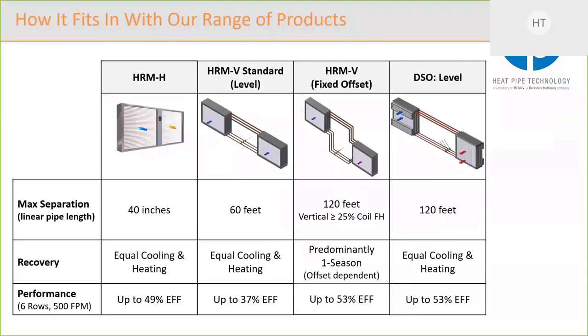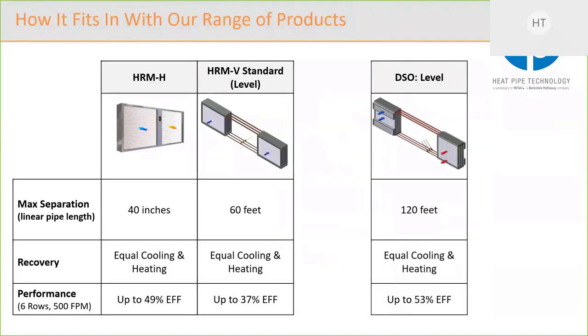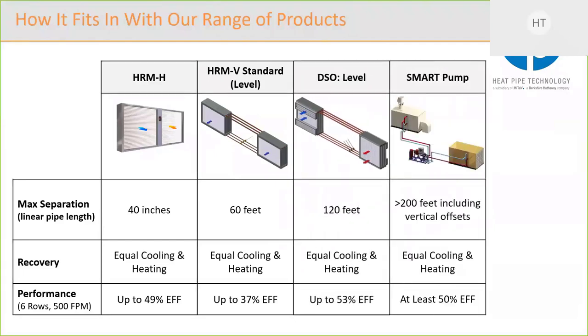So if we continue to look at the equal cooling and heating, the two-season applications, this is where the water system comes in. So what we're looking at here is now not a passive system with no moving parts, but it's actually got a pump that's going to be pumping water glycol mixture around. However, that allows you to go over 200 feet. And that's how this system complements the existing product range.